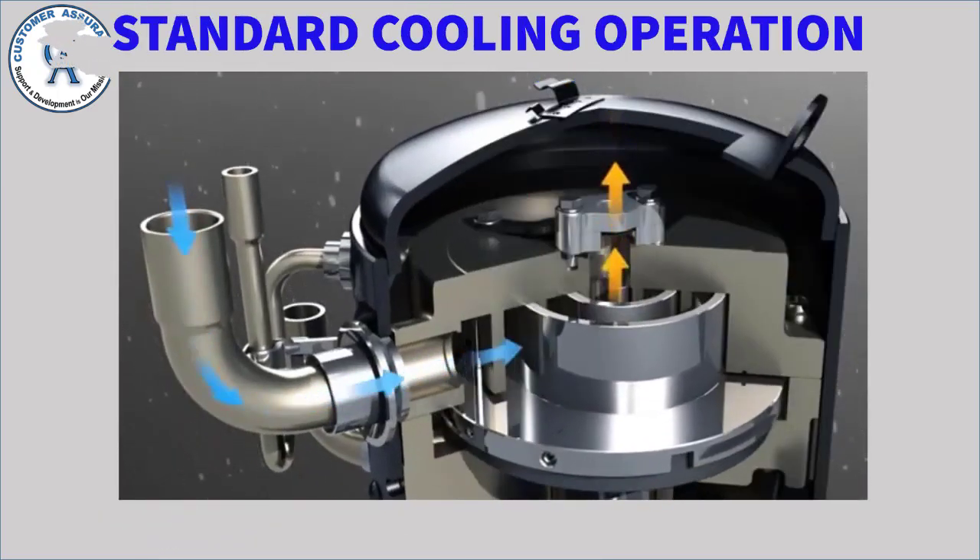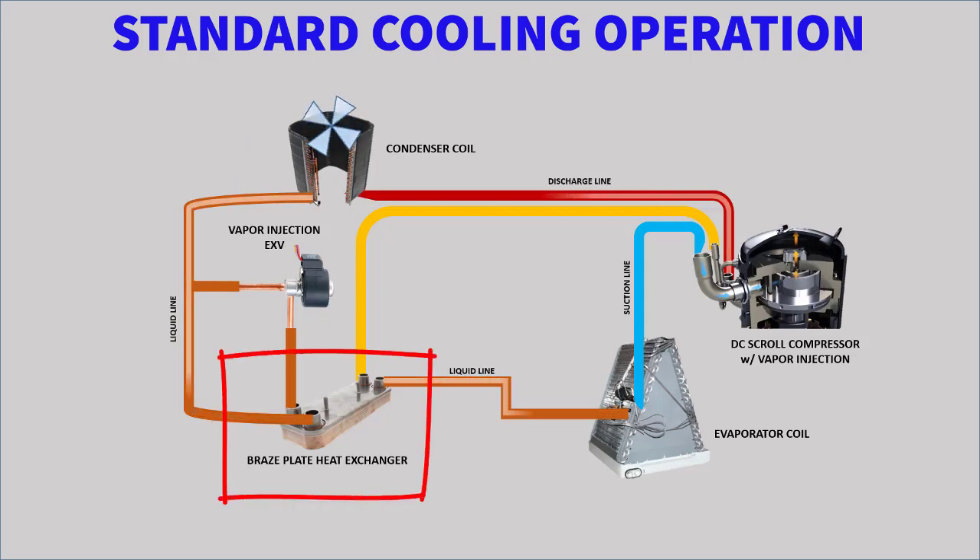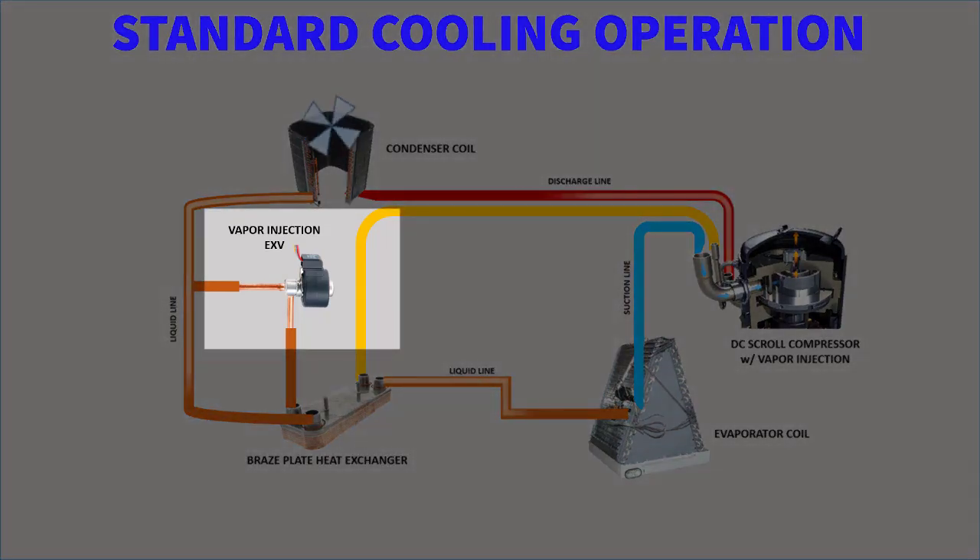On a standard call for cooling, the variable speed scroll compressor will be ramped up by the VFD to the required speed based on the demand. High-pressure refrigerant from the compressor will travel down the discharge line and into the unit's condenser coil. The condenser fan motor, which is controlled by the VFD, will help the condenser reject the heat, desuperheating the refrigerant and eventually condensing it. If the system is properly charged, the liquid refrigerant will be sub-cooled as it exits the condenser coil. The sub-cooled liquid leaving the condenser is routed through the braze plate heat exchanger and from the liquid service valve into the liquid line on its way to the system's evaporator coil. With the vapor injection EXV closed on a standard cooling call, the braze plate heat exchanger has no impact on the system's operation or capacity.